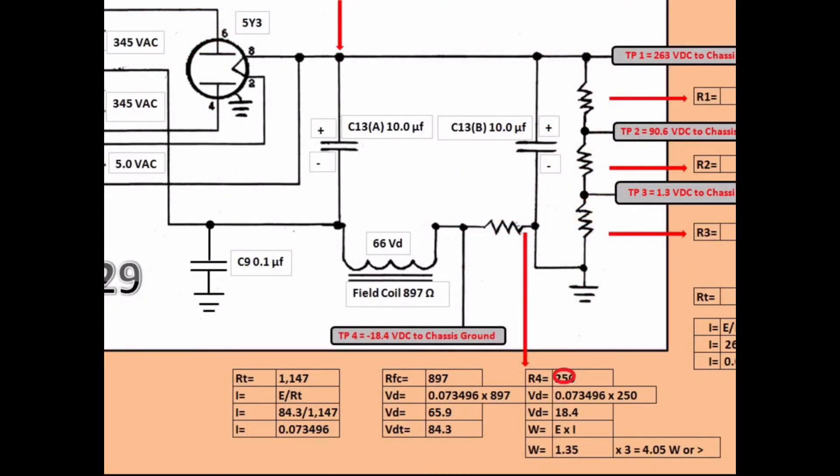To calculate that bottom section, I'm going to take the same formulas that I used above. I'm going to look at the total resistance. I'm going to look at R4, which is 250 ohms. I've got the DC resistance of the field coil, which measures 897, and a total, which is represented by RT of 1147.